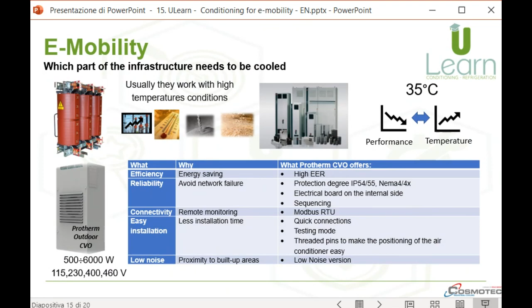The battery for energy storage works at a lower temperature than the inverter device, in the order of 25 degrees. An increase of the temperature produces a quick reduction of the useful life of the battery. For cooling of the energy storage cabinet, Cosmotec offers air conditioners with direct current power supply, with cooling capacity up to 700 watt with the CVO range, and cooling capacity of 1 and 2 kW with the Predator range. The air conditioners are designed to work continuously, giving maximum efficiency and reliability.